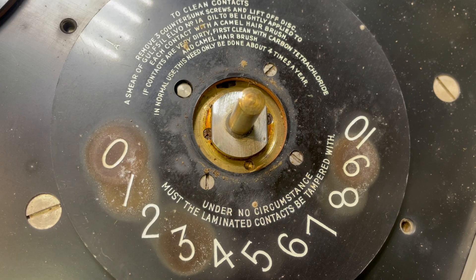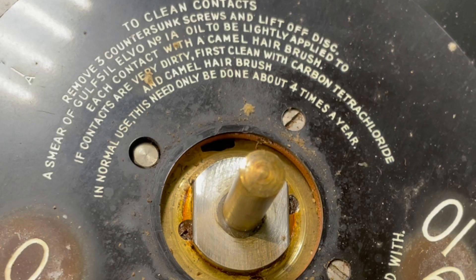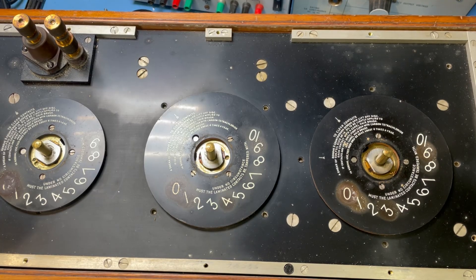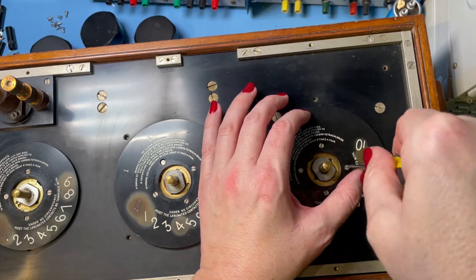So that's just the back of the plate there — I can give this a good clean up while it's off. On here it says: to clean contacts, remove three countersunk screws and lift off disc. A smear of Gulfsil Elvo No. 1A oil to be lightly applied to each contact with a camel hair brush. That's very specific. If contacts are very dirty, first clean with carbon tetrachloride. I'm not sure I have any of that, but what that means is we can take this disc off and give the contacts a good clean up. I normally use IPA and a cotton bud to get into all the difficult areas, and then find something more suitable to lubricate it with.